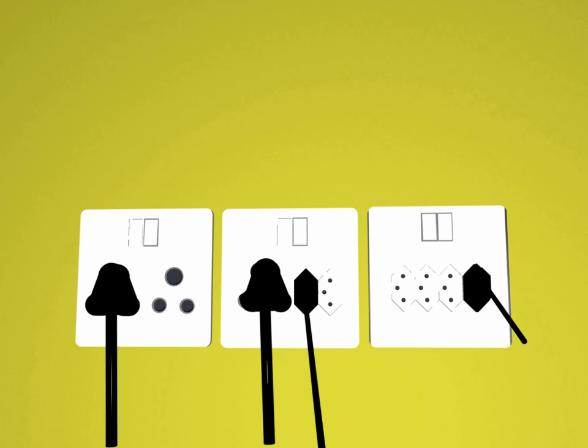IEC 60906-1 plugs are similar in size and shape to the Europlug, with the front profile being a flat hexagon. They are nominally 35.5mm wide. The 3-pin Class 1 plug is 17mm high, whereas the 2-pin Class 2 plug is 14mm high. The parallel side faces are 26mm apart, and the two pairs of side faces are orthogonal to each other.